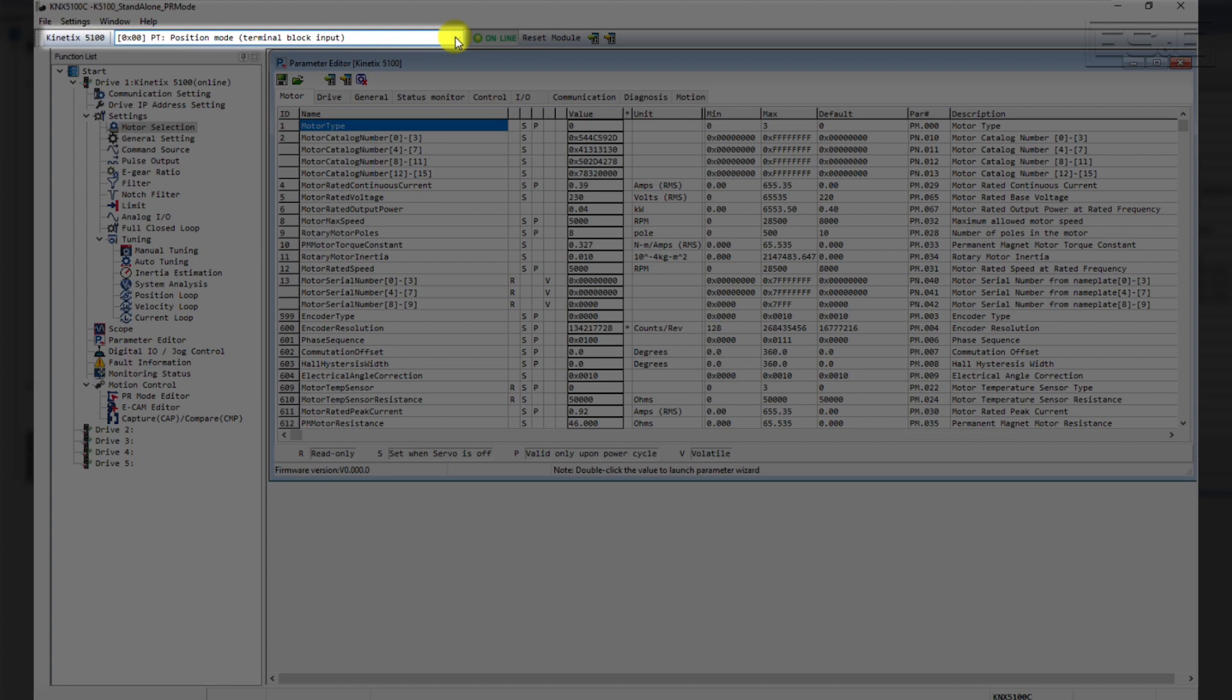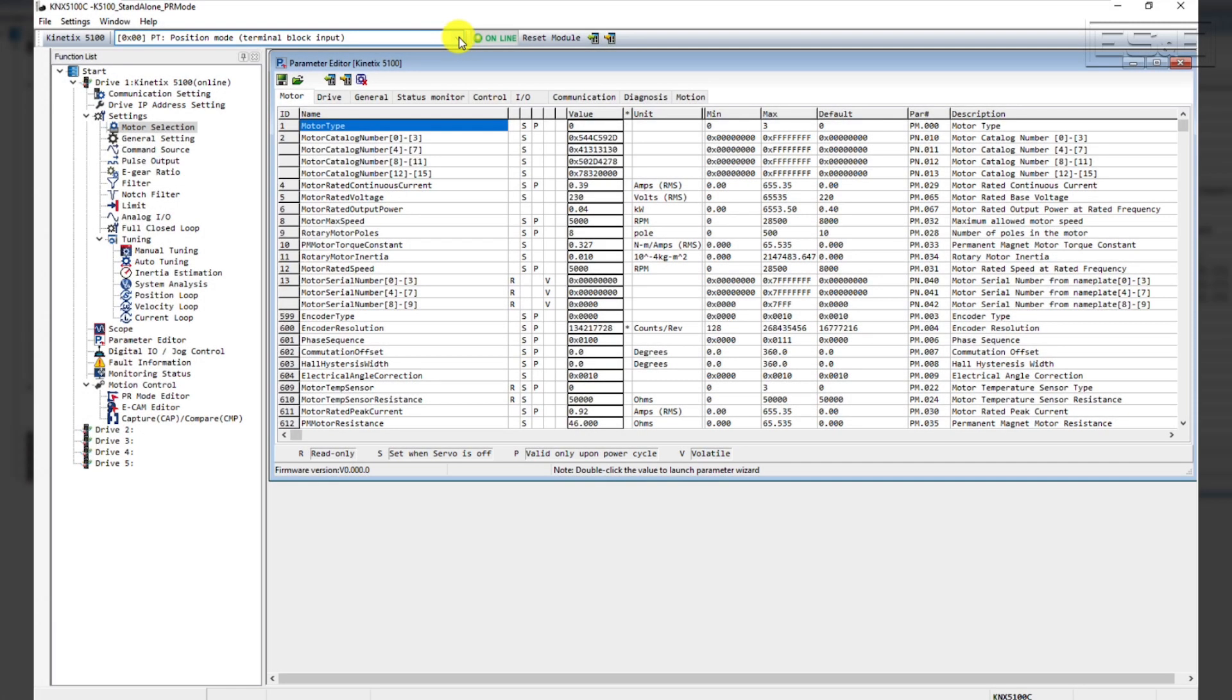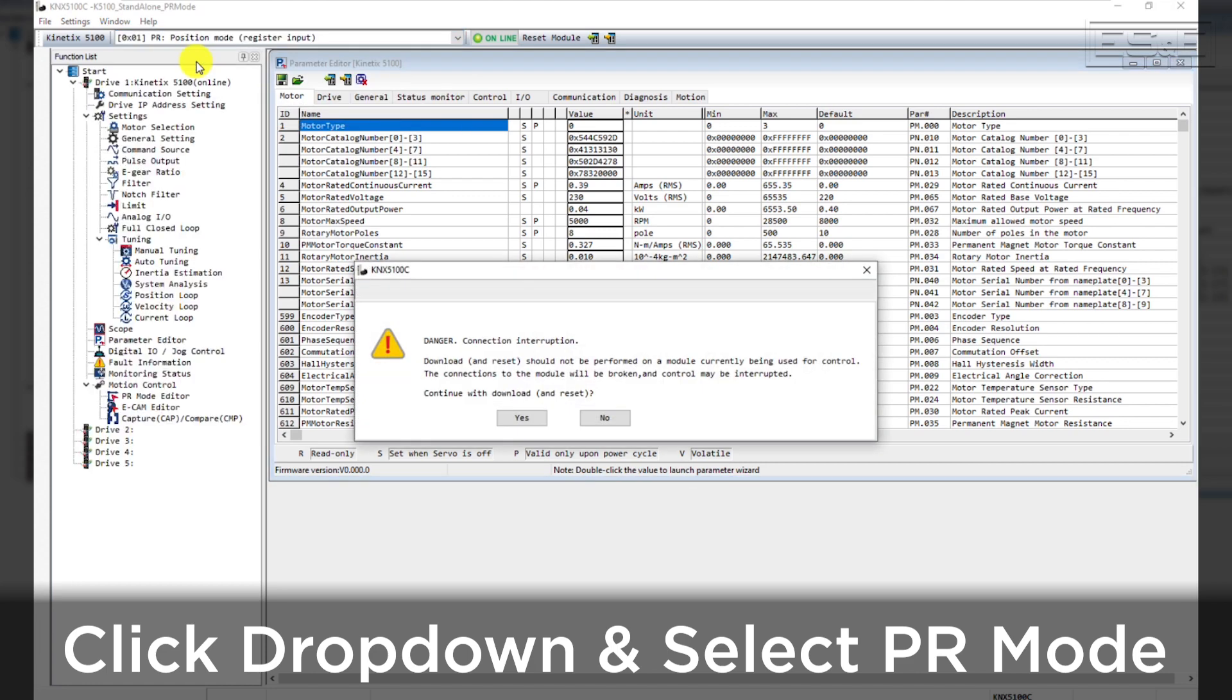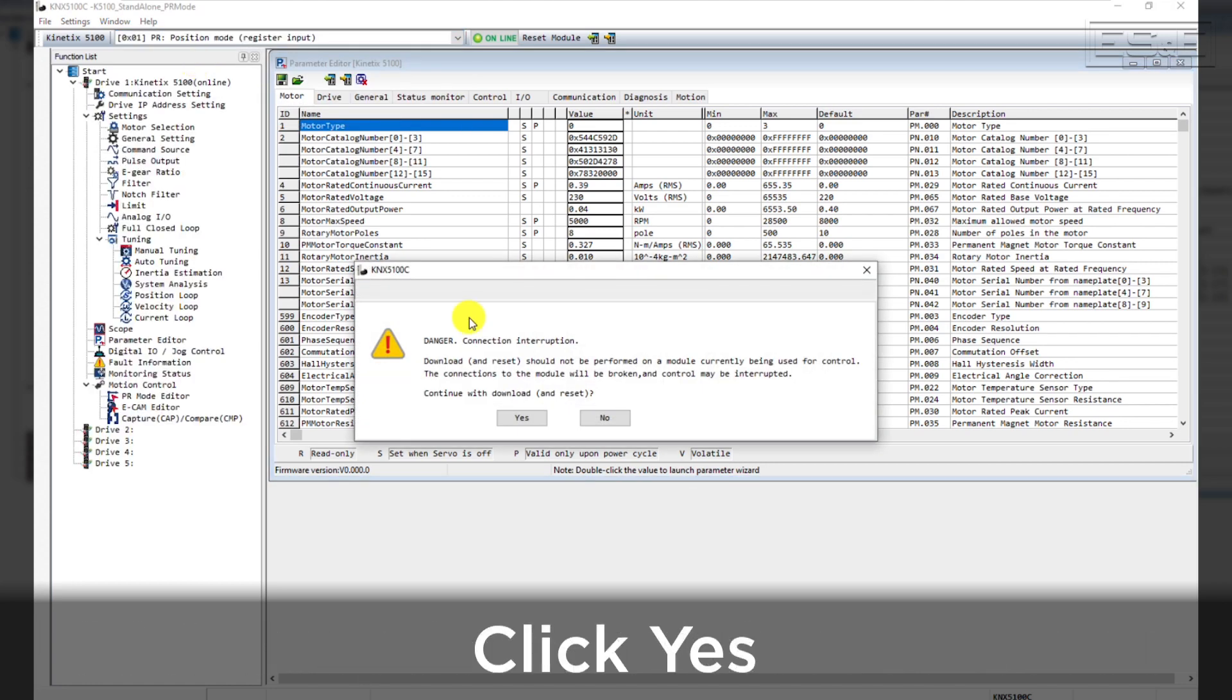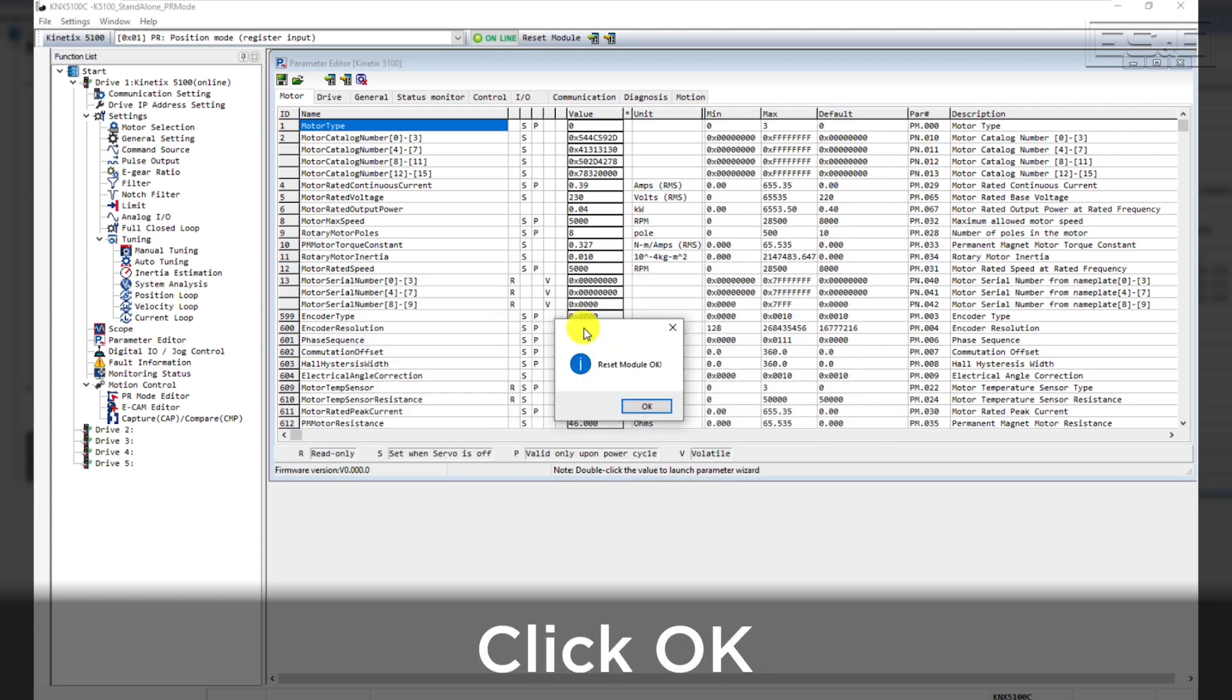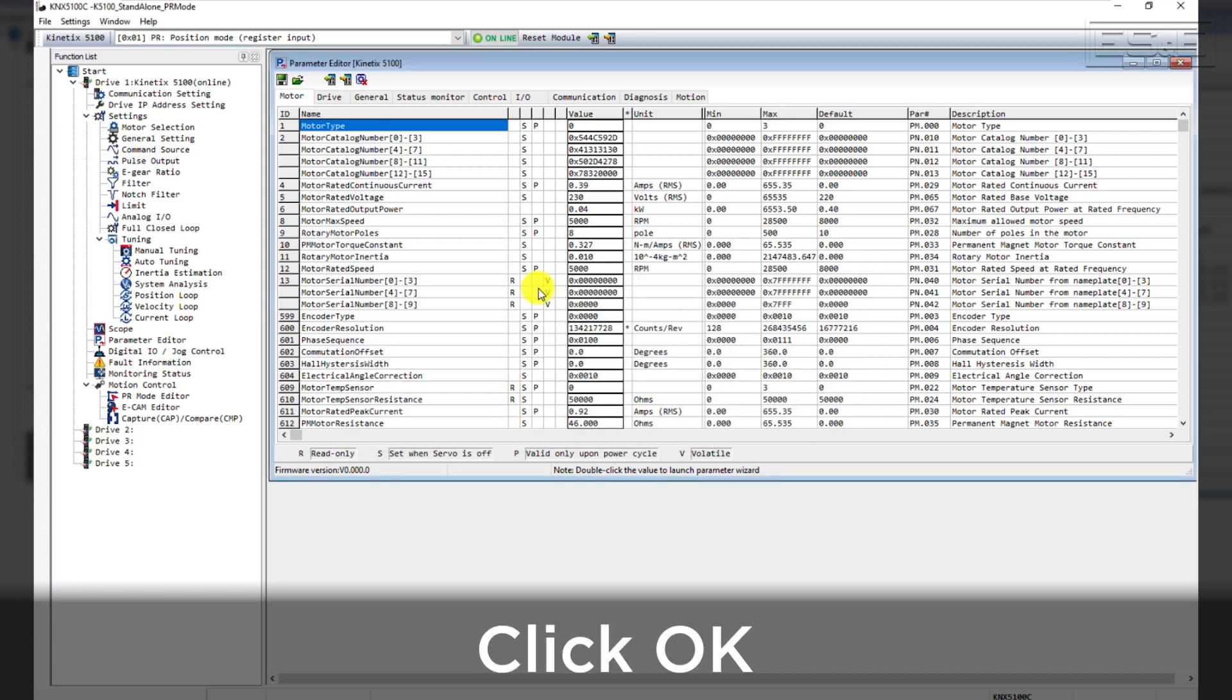The default is set to Position mode or PT mode. Up at the top left-hand part of the screen, there's a drop-down for this mode selection. Click on the drop-down and select PR for Position Register Input mode. Click Yes to continue to download and reset the drive again. Then click OK to the Reset Module OK prompt.